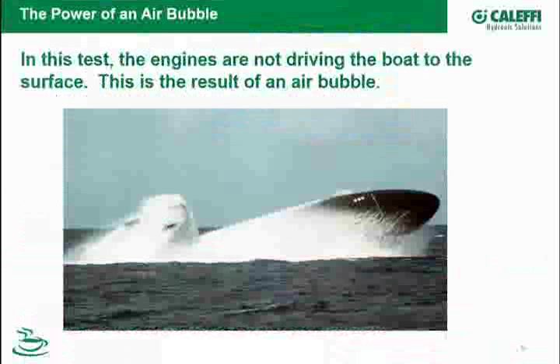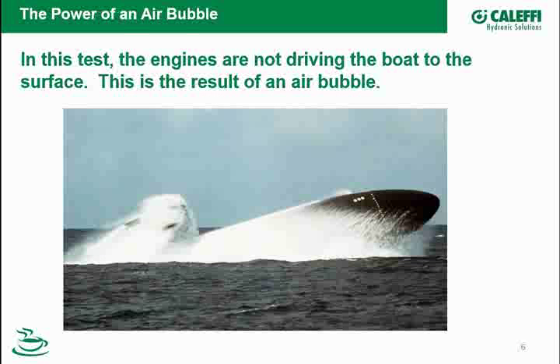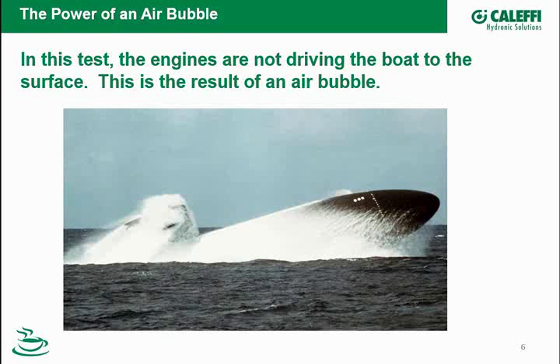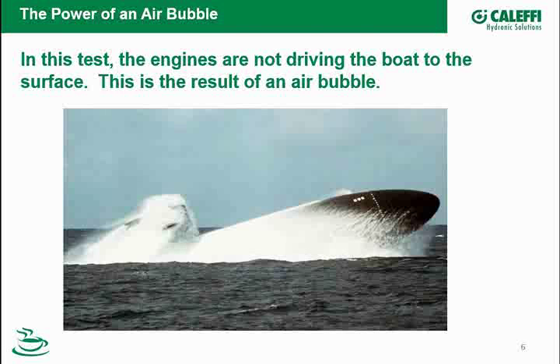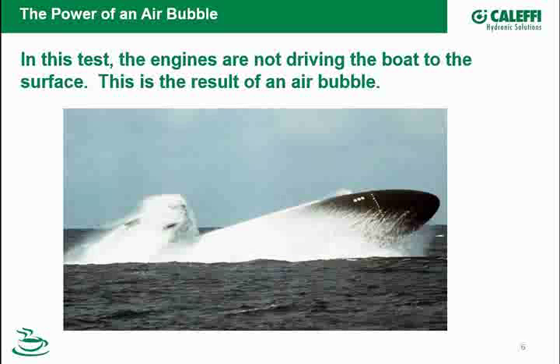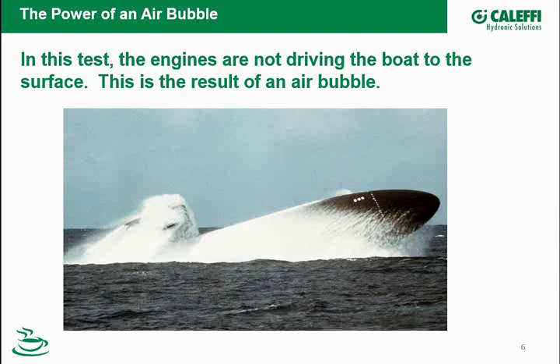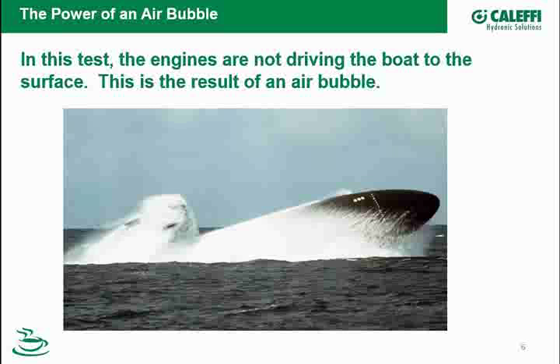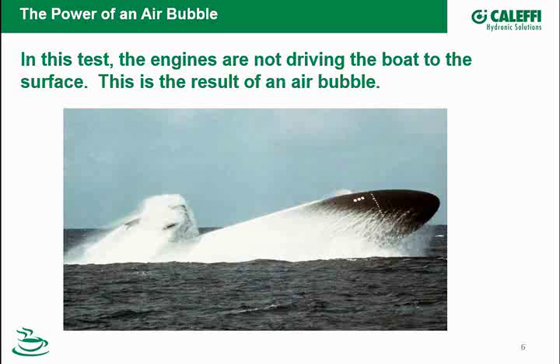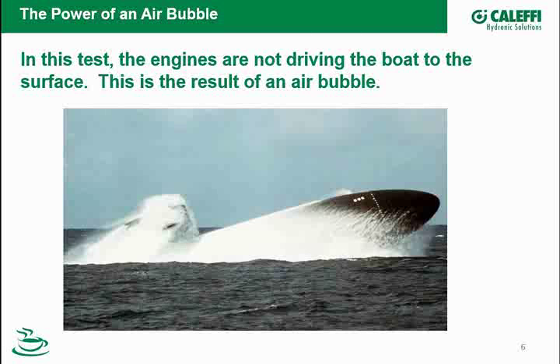Finally, it's really about the power of an air bubble — what's called an emergency blow. If you go on YouTube, there are some nice videos showing the entire process. An emergency blow is done with compressed air causing the submarine to become positively buoyant. So when I look at hydronic system design for air elimination, if I can increase my bubble sizes, those larger bubbles have a higher buoyant force and are much easier to have rise up and separate out.